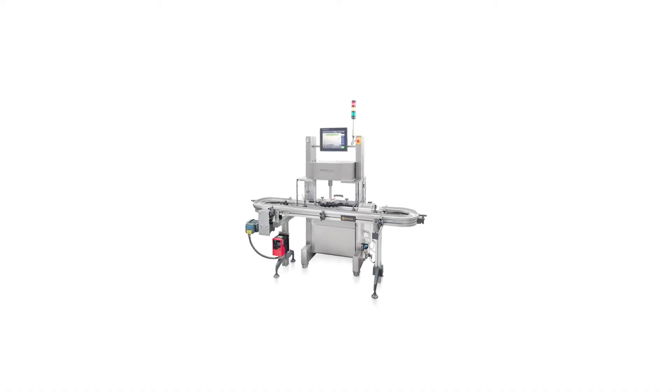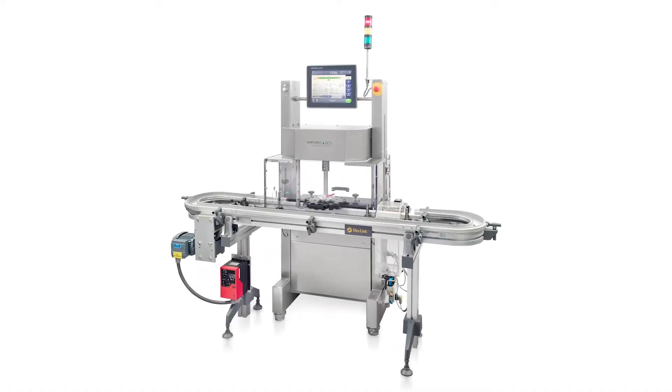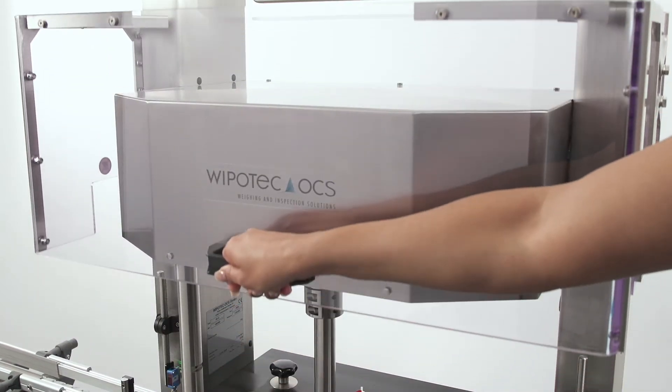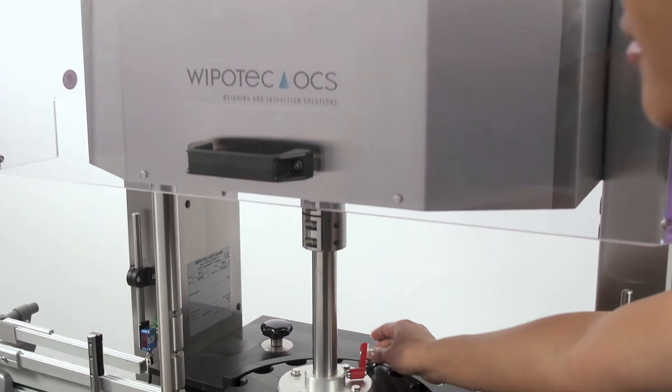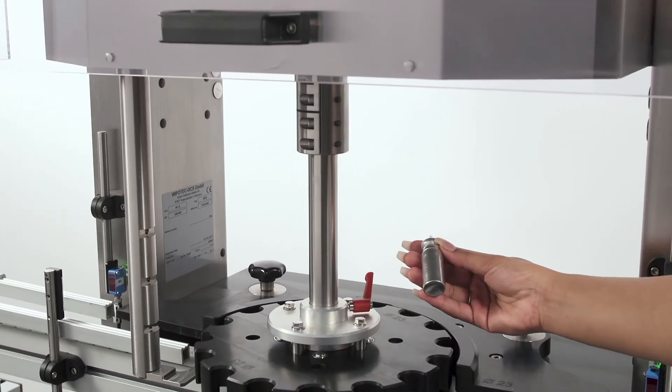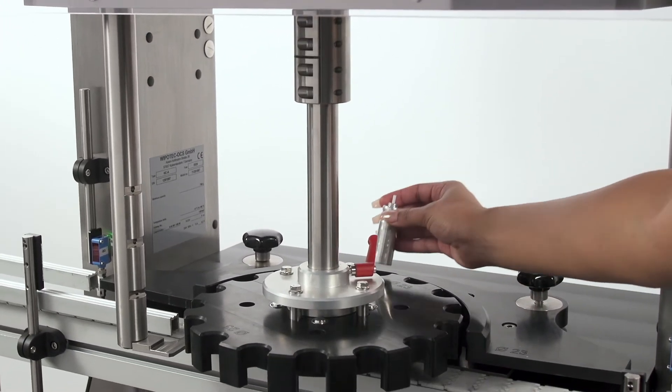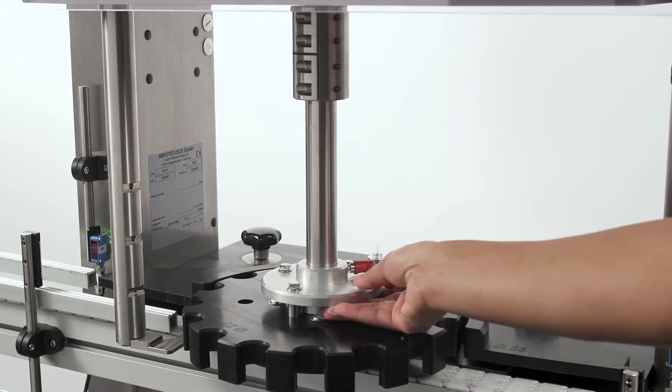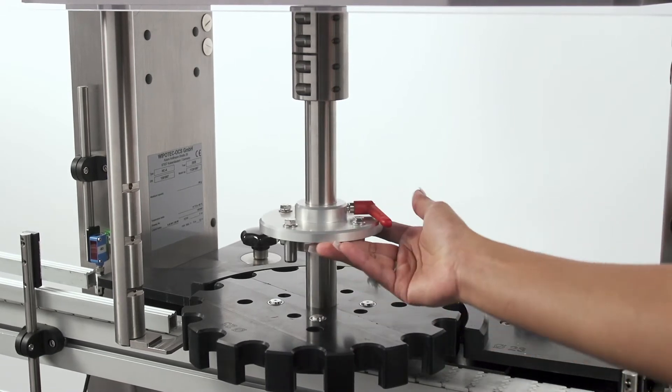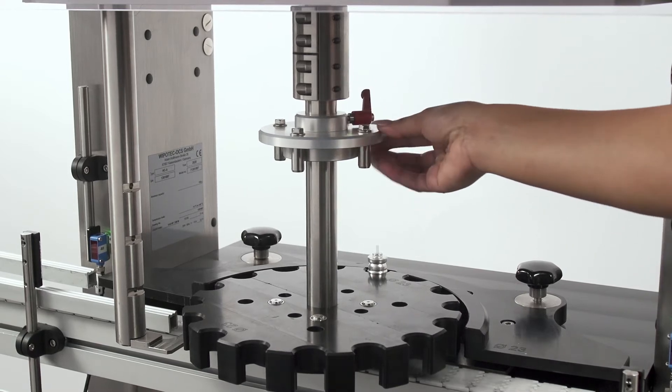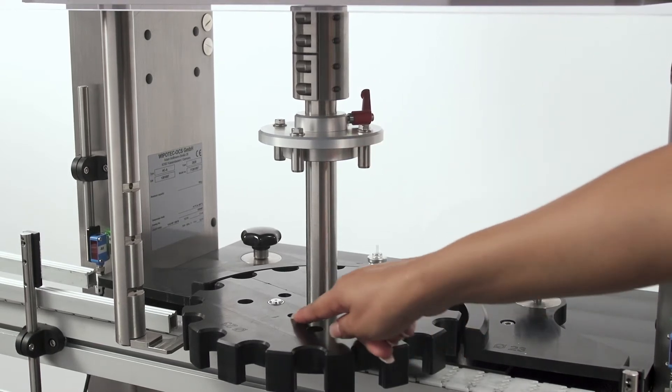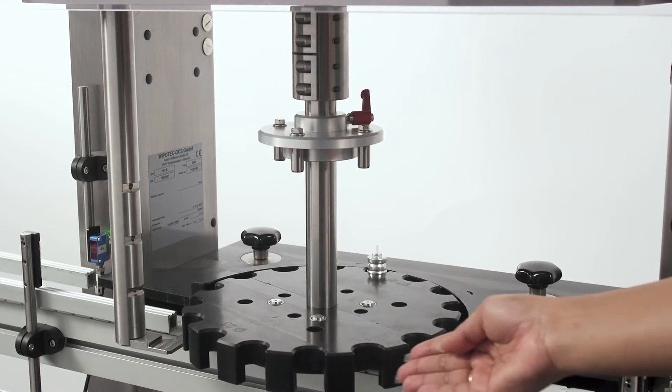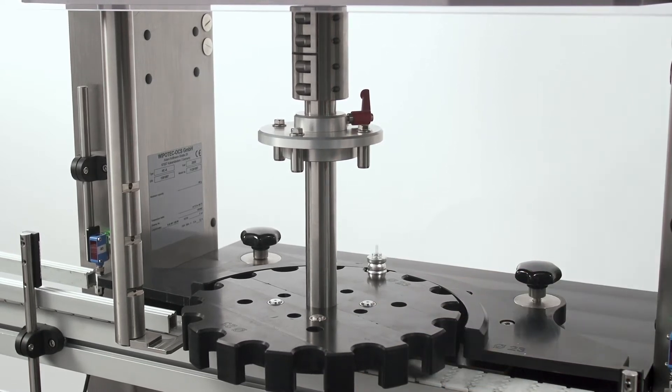Let's take a closer look at the machine's features and configuration options. This machine version is a single position HCAIS checkweigher and it utilizes one EMFR weigh cell. The weigh cell is located under the star wheel and in the back of the machine at the 12 o'clock star wheel position. The lever you see above the star wheel enables a tool-less removal of the star wheel. It is important to make it easy to change the star wheel because this allows the customer to quickly change the production line over to run new products with a different diameter through the checkweigher.